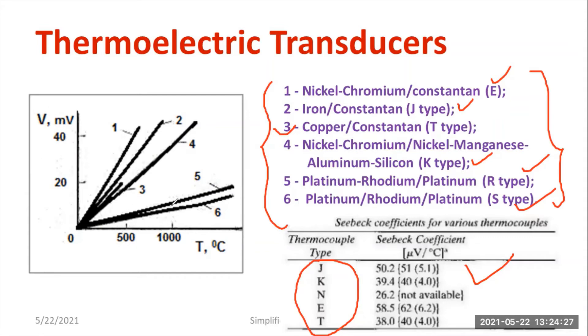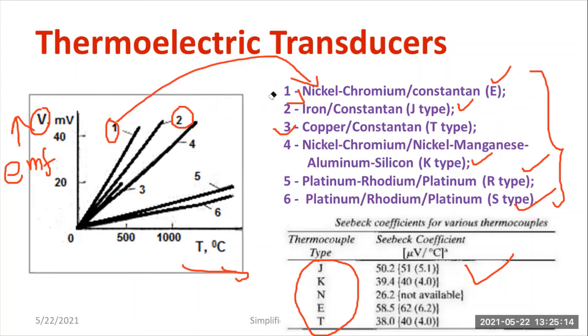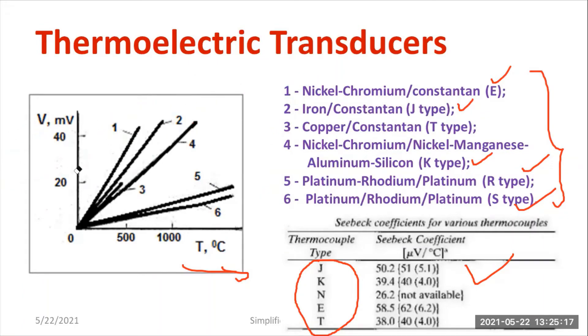A graph shows EMF versus temperature, with the difference in temperature on the x-axis and EMF on the y-axis. With respect to change in temperature, there will be production of EMF. Different combinations — such as nickel-chromium (E-type) and iron-constantan (J-type) — produce different graph profiles. Some combinations show a linear scale, but in some cases it goes non-linear, and that is a drawback of the thermoelectric transducer.